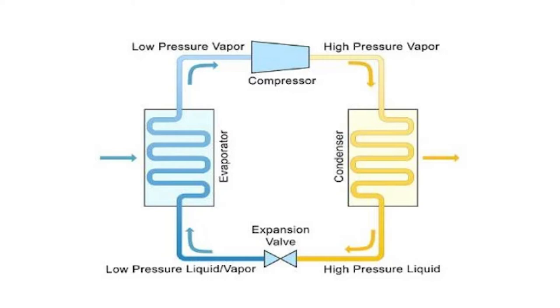Any temperature increase that occurs after the change of state is known as superheat, and can be defined as the difference in temperature between the refrigerant leaving the evaporator and the saturation temperature of that refrigerant.